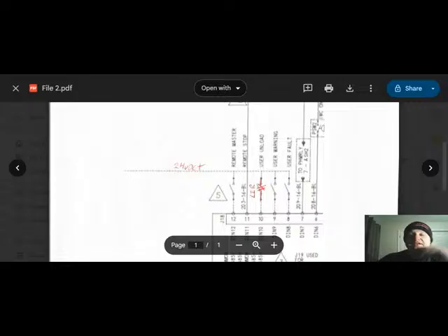It'll run for its designated time, whatever that is, 10 minutes, 5 minutes, whatever, and then it will go into standby and wait for this signal to go away. So when you come in the morning and put the lights back on, this opens, and the compressor says, hey, it's time to get to work. So it loads and locks and rolls. This is what I would call a basic interface right here. This is pretty simple and just about anybody can get it.